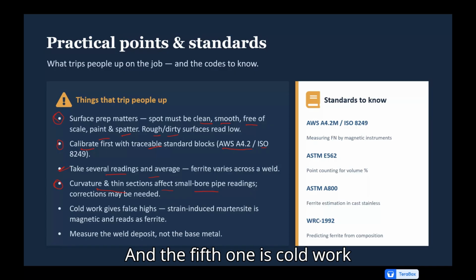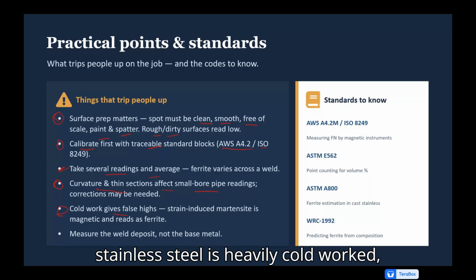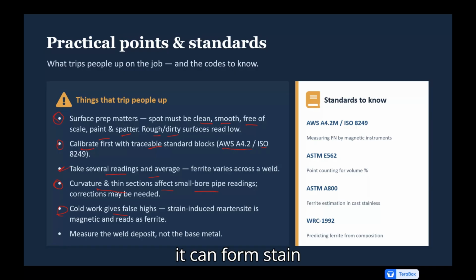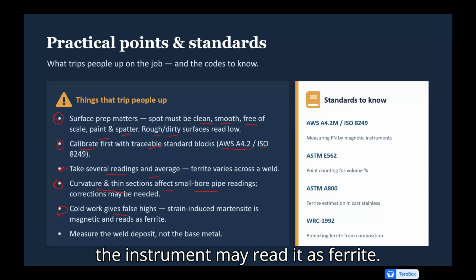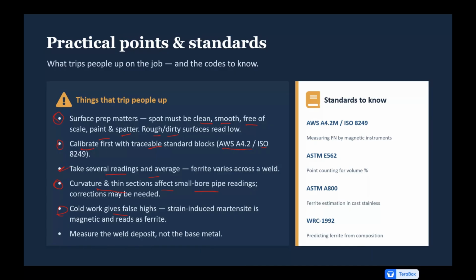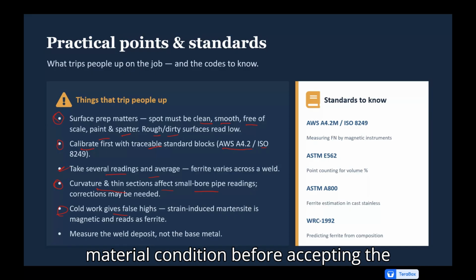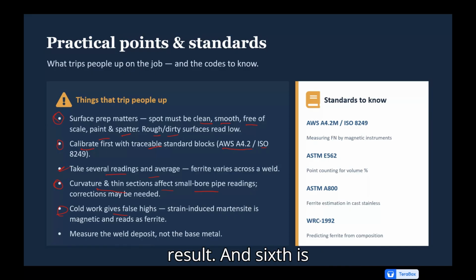And the fifth one is cold work can give false high readings. When austenitic stainless steel is heavily cold worked, it can form strain-induced martensite. So martensite is magnetic. So the instrument may read it as ferrite. This can give a falsely high ferrite reading. So the inspector must understand the material condition before accepting the result.